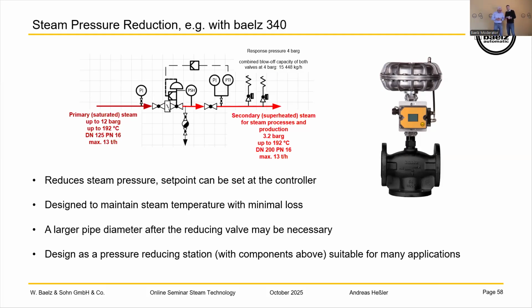A question from the audience has to do with the steam valve, the 340, when we use it for condensate side control. How would the steam valve ensure the safety function? Normally with springs. Here you can see a picture with a pneumatic actuator. In the pneumatic diaphragm actuator you normally have springs, and when the air fails, the springs will close the valve, or you put them on the underside and the valve opens. But in a safety valve, you want to close it. So this safety function is already included: no power to the valve means closing the valve.